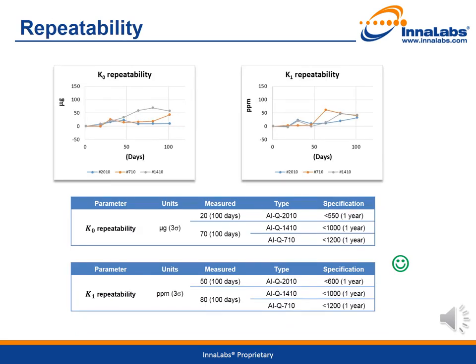The long-term repeatability figures are derived from a test in which measurements are taken under constant conditions, and between successive measurements the accelerometers are exposed to temperature variations. For this purpose, a real-time aging program was introduced, in which a four-position test over temperature is performed every two weeks. In between, the accelerometers are stored in normal storage conditions at ambient temperature and regular atmosphere. 100 days of data have been gathered from three randomly chosen units, and testing is ongoing. The worst-case results were taken from the recorded data. While the measurements have yet to complete the full one-year target time, the data thus far suggests that the final values should be significantly within the specification limits for all variants.